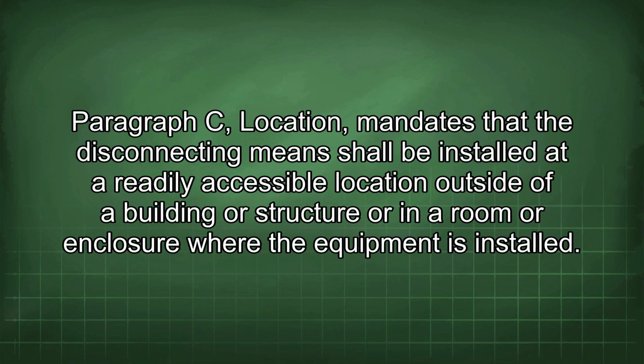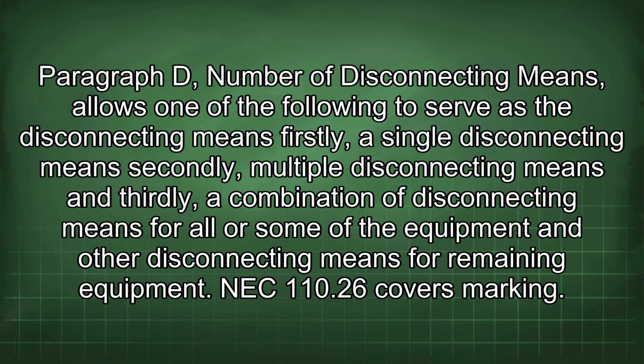Paragraph C, Location, mandates that the disconnecting means shall be installed at a readily accessible location outside of a building or structure or in a room or enclosure where the equipment is installed. Paragraph D, Number of disconnecting means, allows one of the following to serve as the disconnecting means: firstly, a single disconnecting means; secondly, multiple disconnecting means; and thirdly, a combination of disconnecting means for all or some of the equipment and other disconnecting means for remaining equipment.